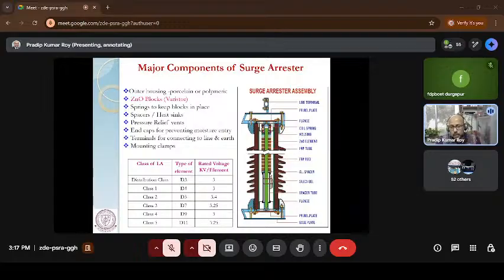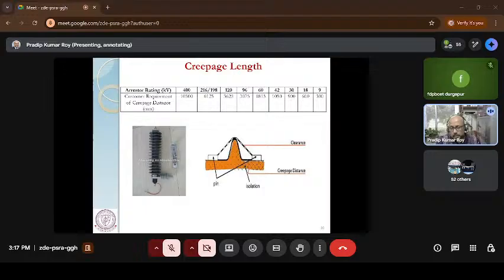Ideally, when the surge comes, it will pass through the block to the ground, not through the surface of the porcelain block. So in that case, your creepage length will depend on where you are going to install. If it is a polluted area, your creepage length will be high. If it is a less polluted area, your creepage length should be low.